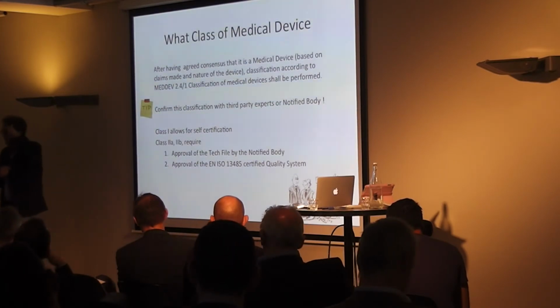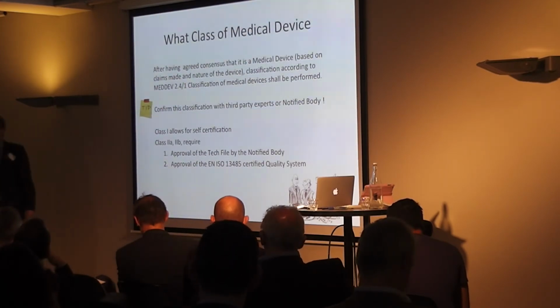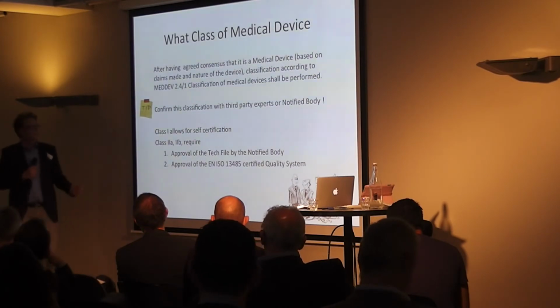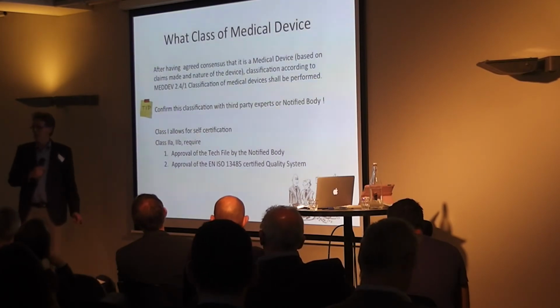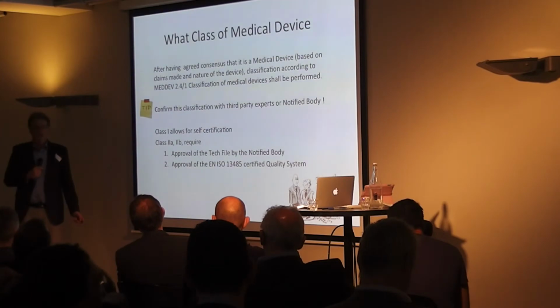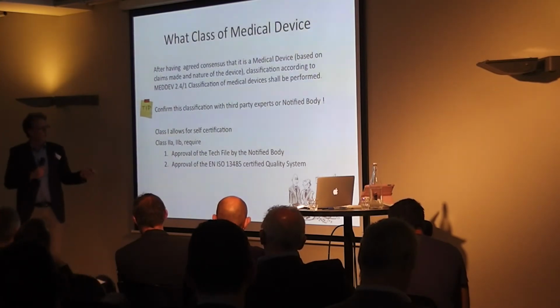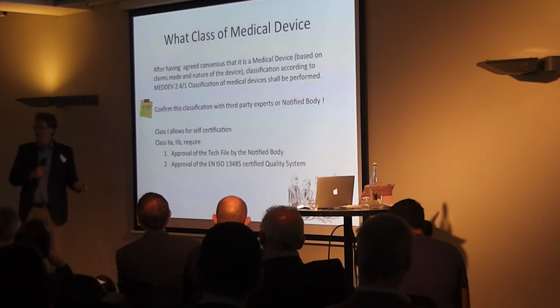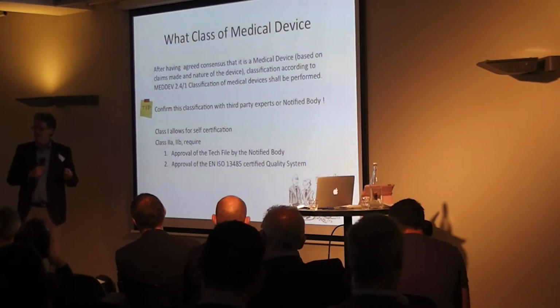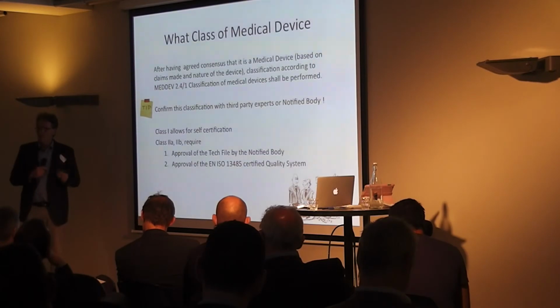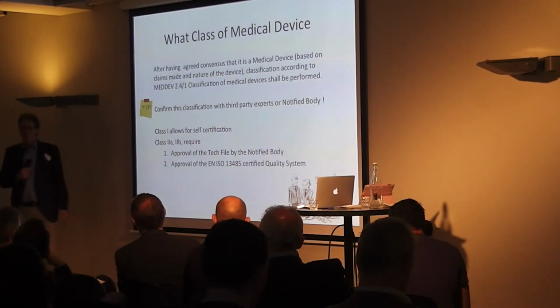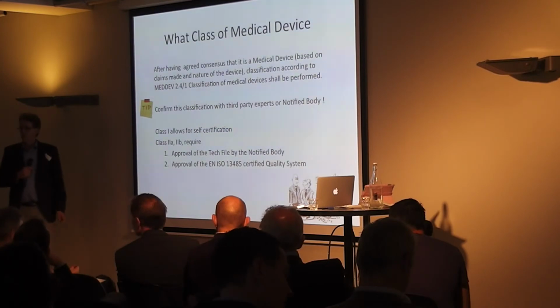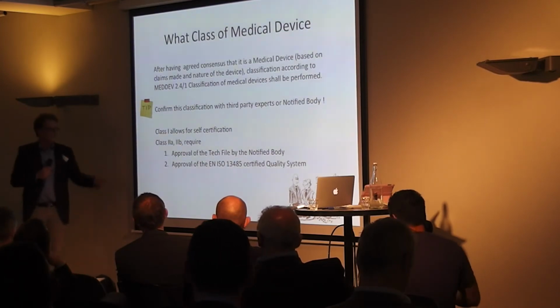And if you bring a class 1M device, M stands for measuring, it sets specific requirements for the accuracy of the measurement function. If you bring a measurement function into your app, measuring specific SI values, then this will be a class 1M device, which you would also need to take to the notified body.